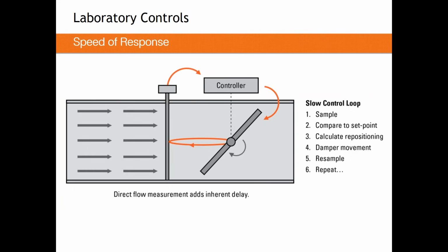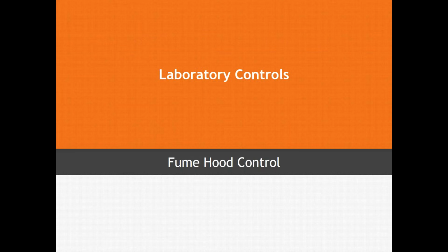This is important to define because your sash does take a second or 2 to open. You can open them at a rate of about 1.5 feet per second. The commonly accepted time that is okay is 3 seconds or less. We're going to dig into this a little bit more when we get now into fume hoods.